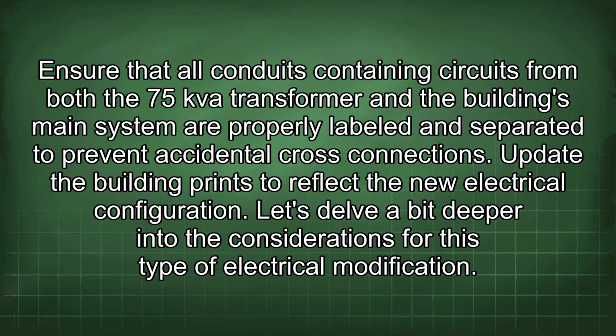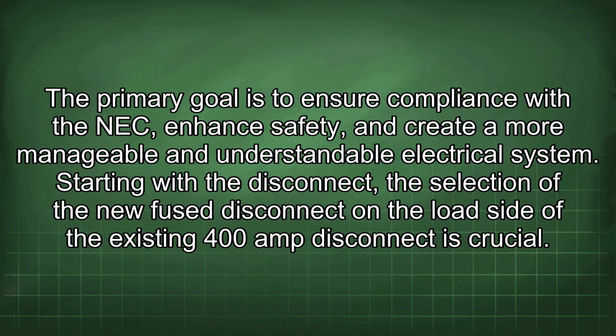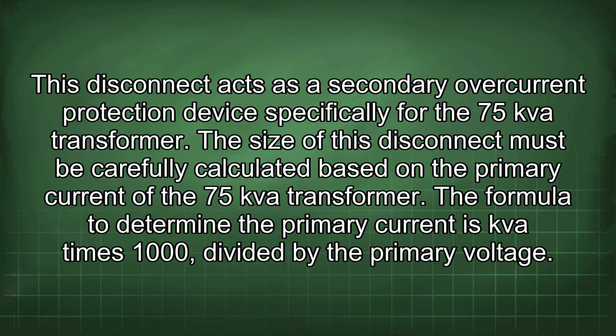Let's delve a bit deeper into the considerations for this type of electrical modification. The primary goal is to ensure compliance with the NEC, enhance safety, and create a more manageable and understandable electrical system. Starting with the disconnect, the selection of the new fuse disconnect on the load side of the existing 400 amp disconnect is crucial. This disconnect acts as a secondary overcurrent protection device specifically for the 75 kVA transformer. The size of this disconnect must be carefully calculated based on the primary current of the 75 kVA transformer.